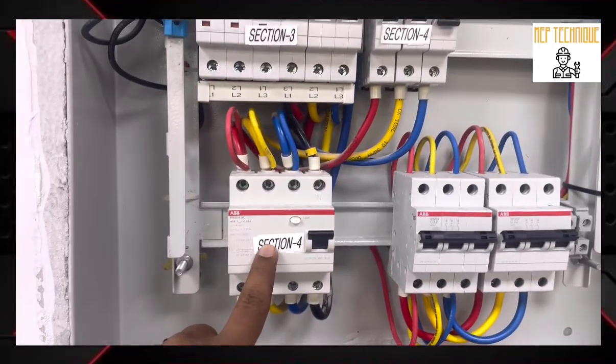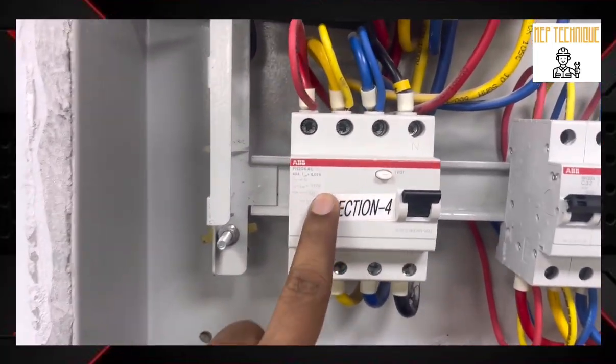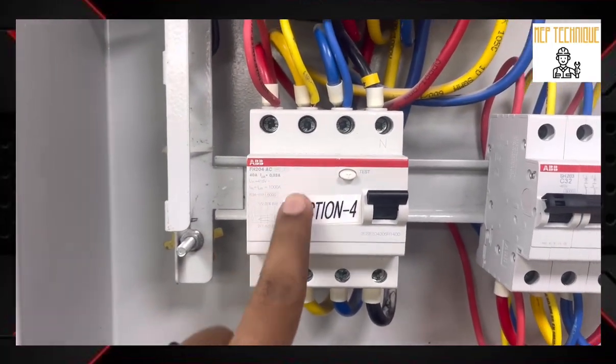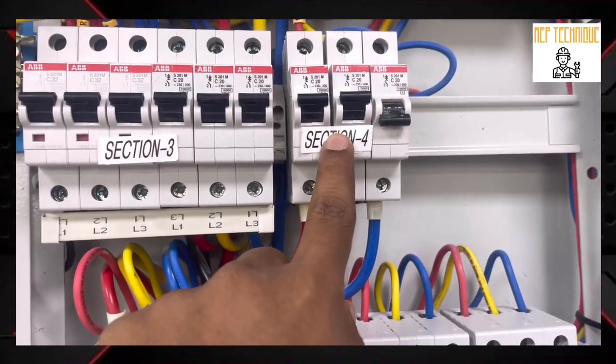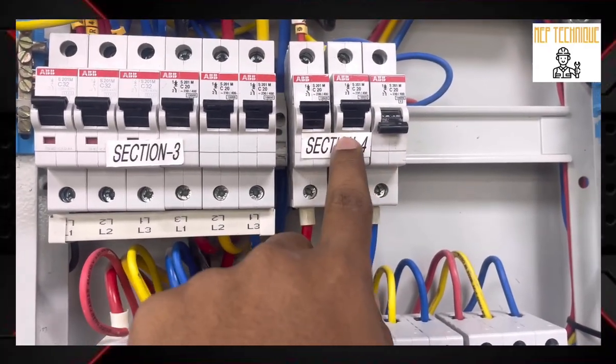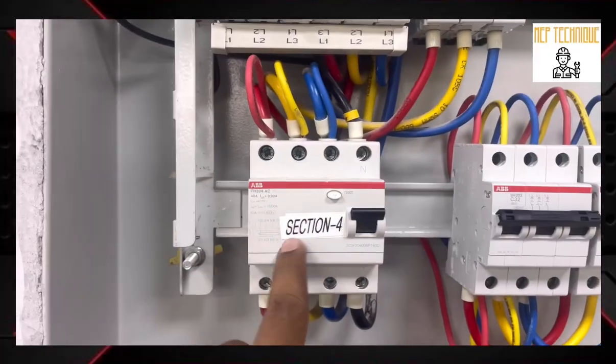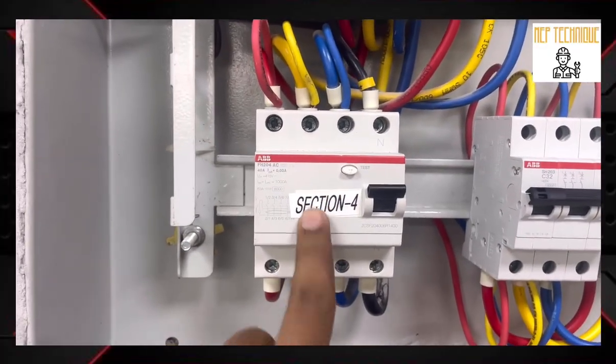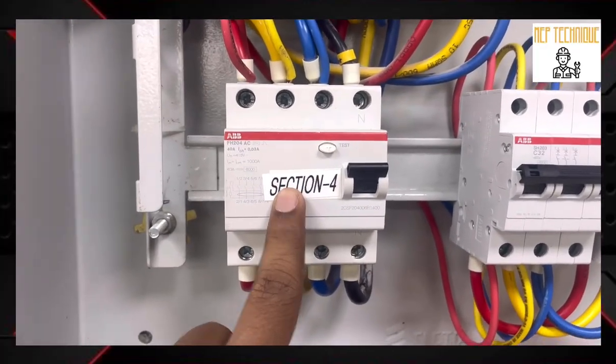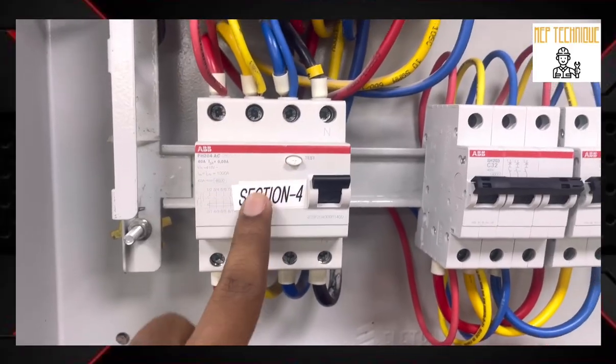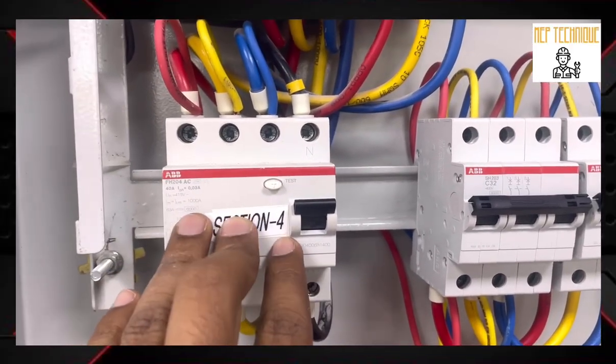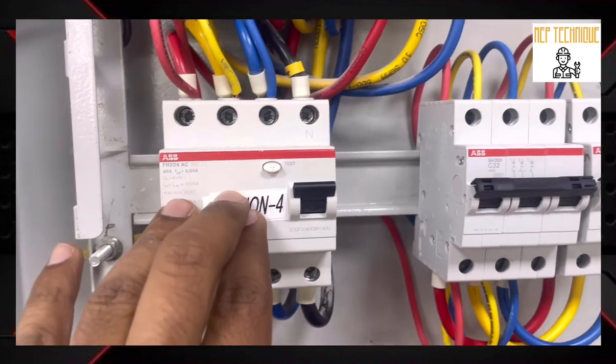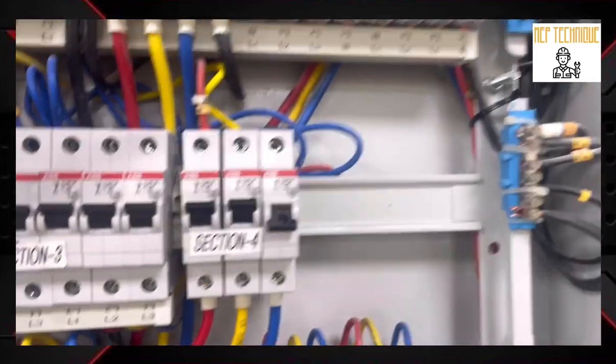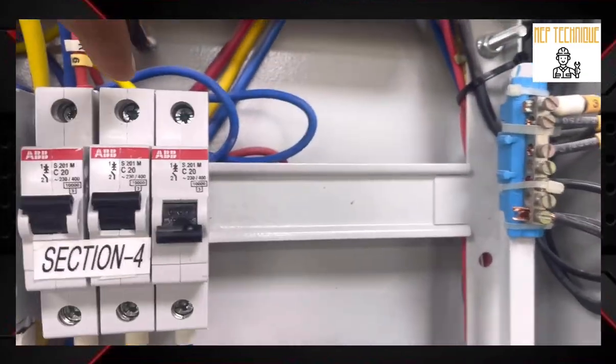This is the ELCB, or you can say RCCB, residual current circuit breaker, where 3 MCBs are connected. These are the 3 MCBs, 1, 2, 3. These are connected with this ELCB. This ELCB is getting tripped frequently due to earth leakage current. So let us identify from which circuit the earth leakage is occurring, because you can see here there are 3 circuits: R6, Y6 and B6.